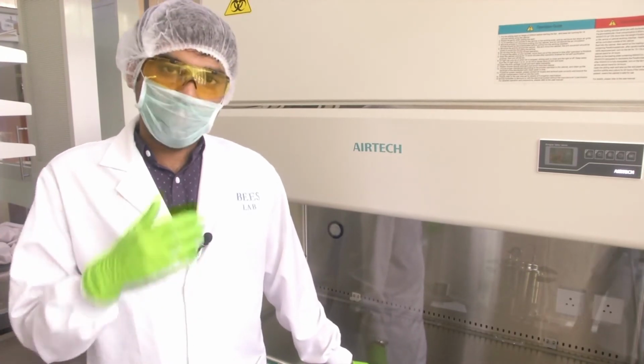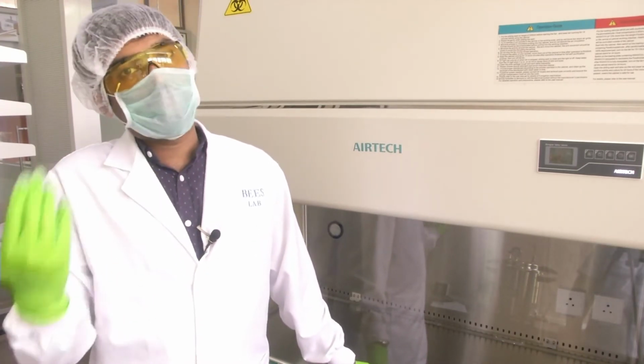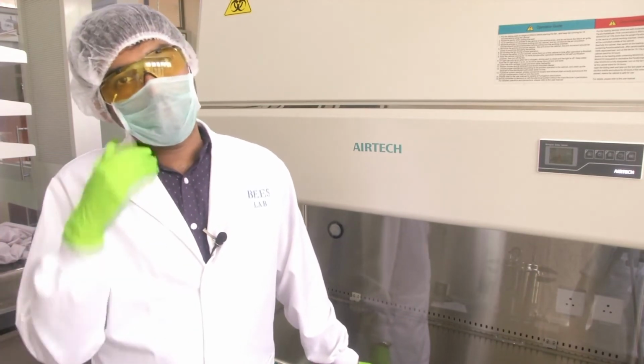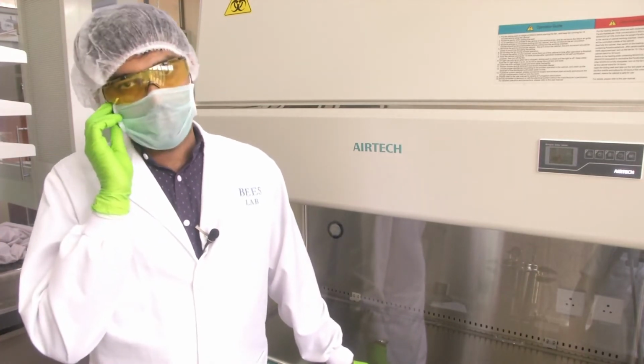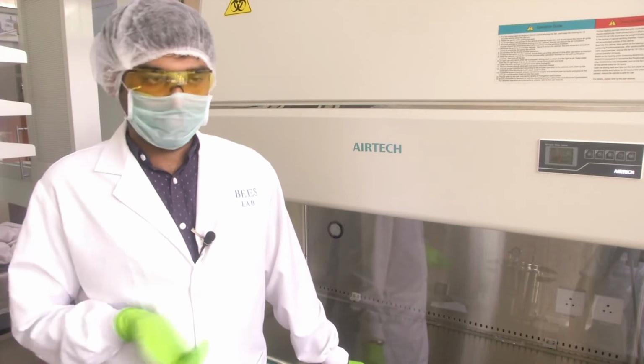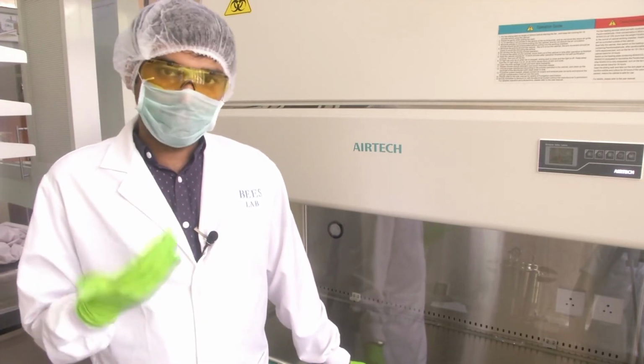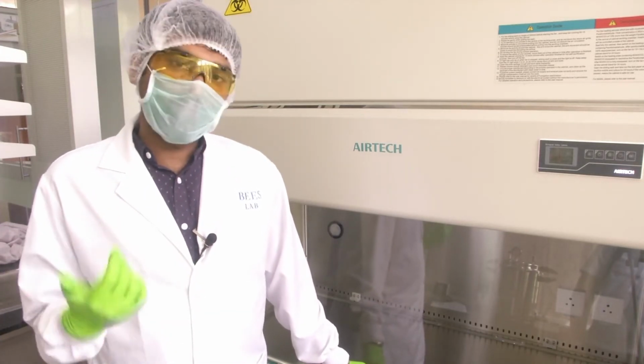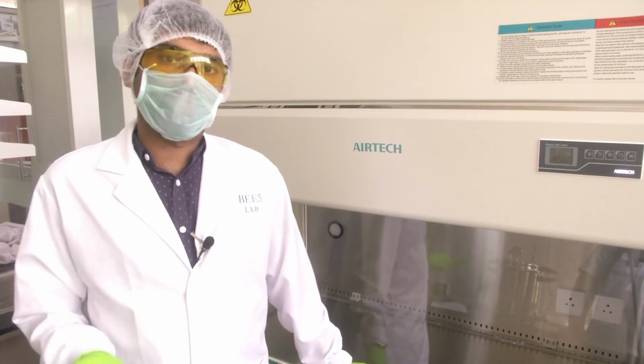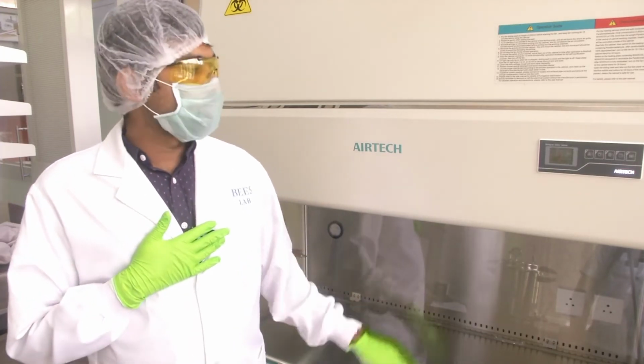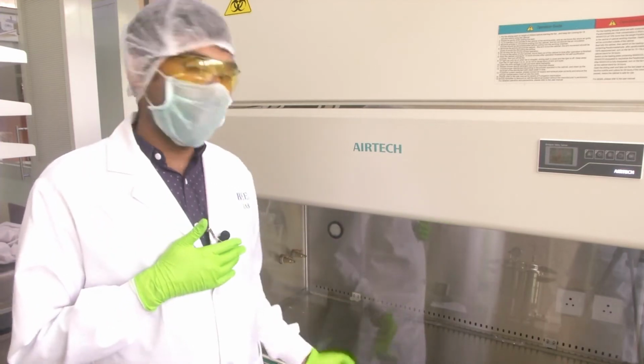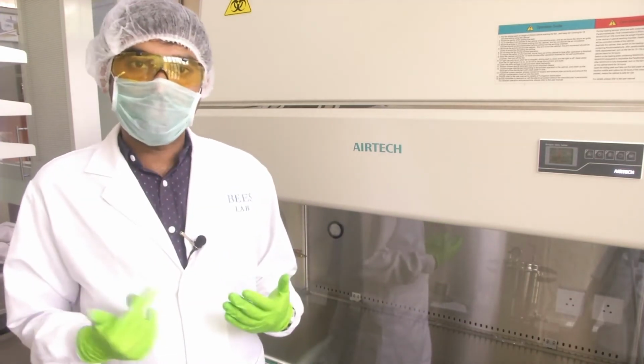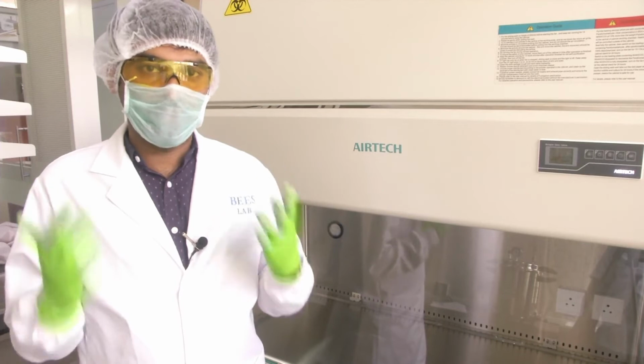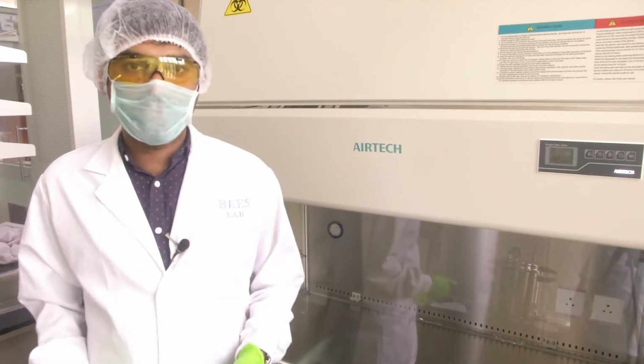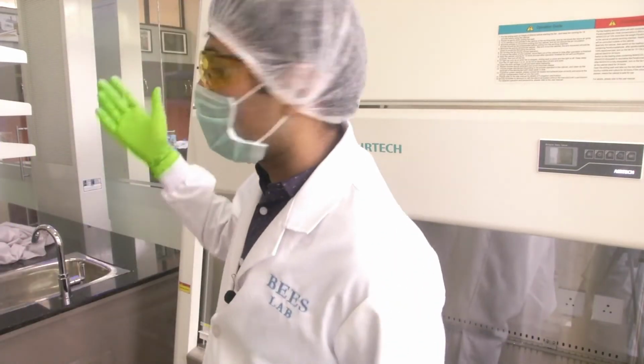A class 2 biosafety cabinet. Class 2 biosafety cabinet would include BSL 2 and BSL 3, biosafety level 2 and 3. A class 2 biosafety cabinet would provide all 3 types of protection, that is personal protection, environmental protection and product protection. How does it do this? It does this through HEPA filters. We have already covered what HEPA filters are, what tower modules are. We have tower modules in this lab, we have seen it.